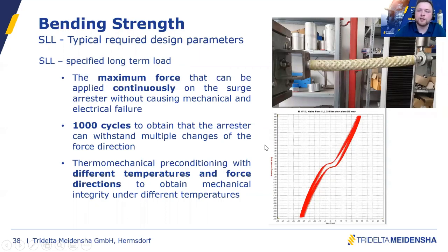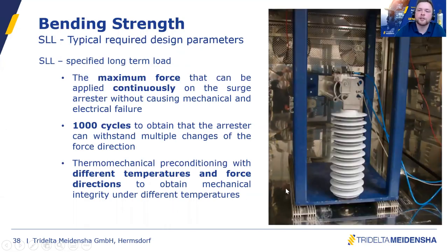And then some other things are done, like a thermomechanical preconditioning, which is a very interesting test where different temperatures and different force directions are tested. You see here an apparatus like this standing in a climate chamber where the temperature goes to plus 40 degrees and to minus 40 degrees, or like we have tested very recently, minus 60 degrees, which is also challenging in this test.